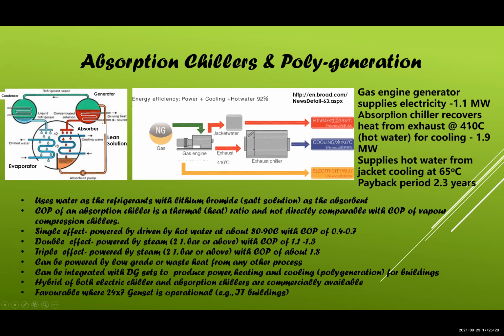It's huge ones. I've given one example here where they have recovered heat from a 1.1 megawatt gas engine. It takes heat from exhaust to get hot water and run the chiller, and then the gas engine jacket is cooled, giving hot water. Because in a gas engine, about 30% goes to electricity, about 30% goes to exhaust, 30% goes to jacket. Approximately one third will go to each. So you can get one third of the heat utilized to produce almost equivalent of cooling in kilowatt. So it has a lot of benefits. So I'll stop here. Thank you very much.